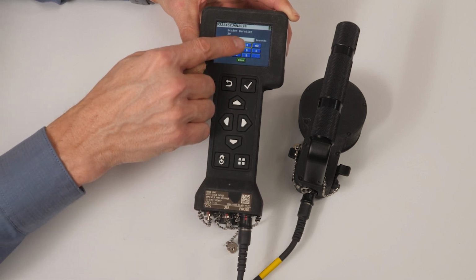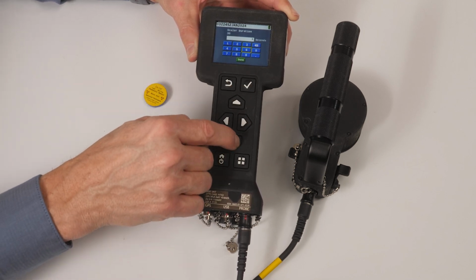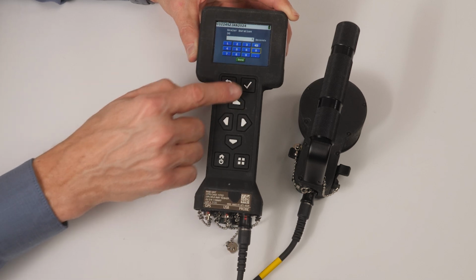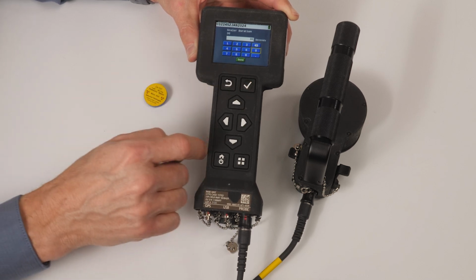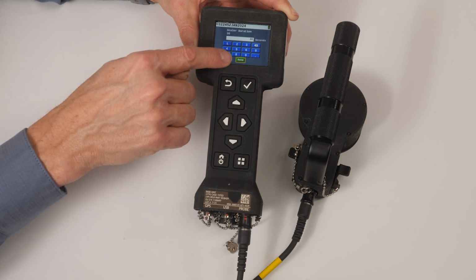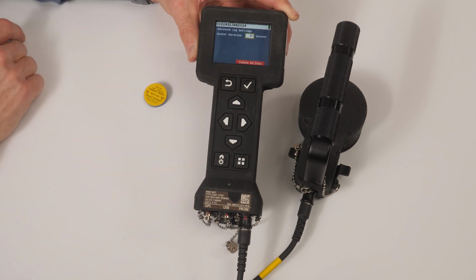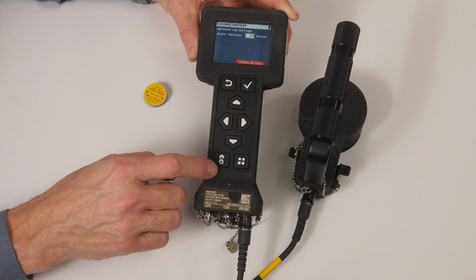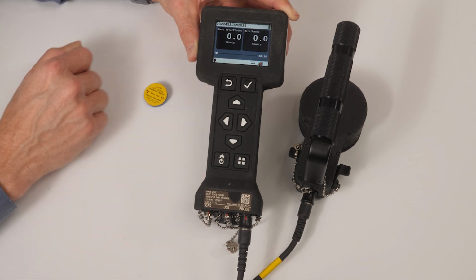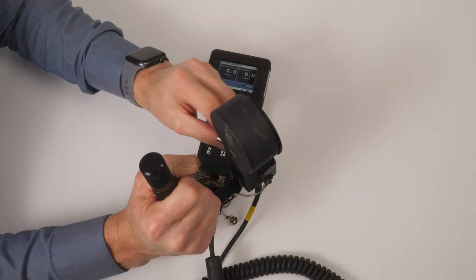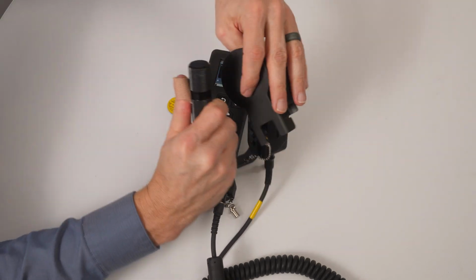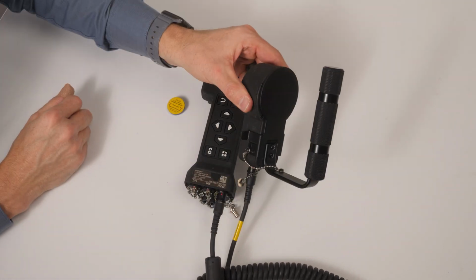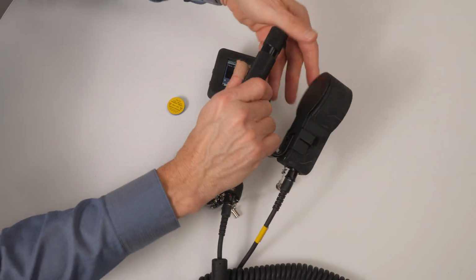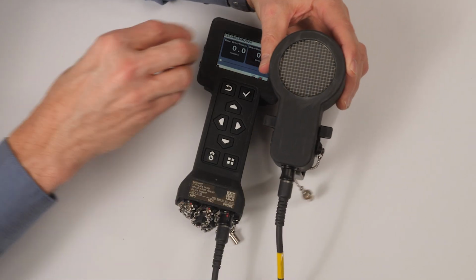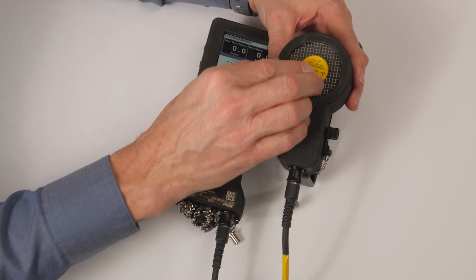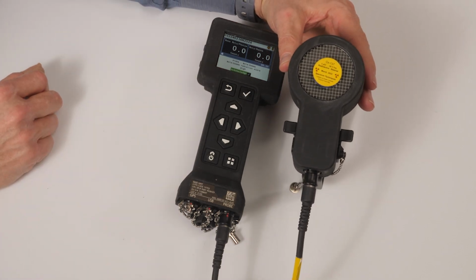To set the scaler duration to 30 seconds, highlight the 3 on the data entry screen using the arrow keys, then press enter key. Then highlight the 0 using the arrow keys, and then press the enter key again. Use the arrow keys to highlight the done button, press enter. Press the home power key to return to the home screen. Remove the SABG protective cover and place it on top of the detector housing. Place the cesium-137 check source in direct contact with the probe etch screen in the center with the labeled side of the check source away from the probe.